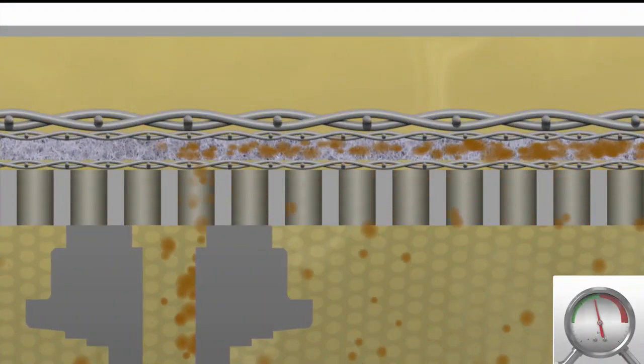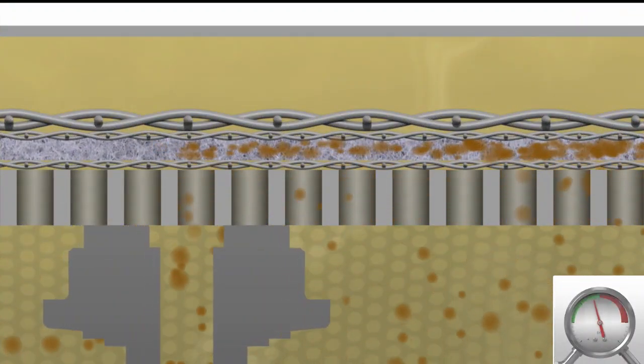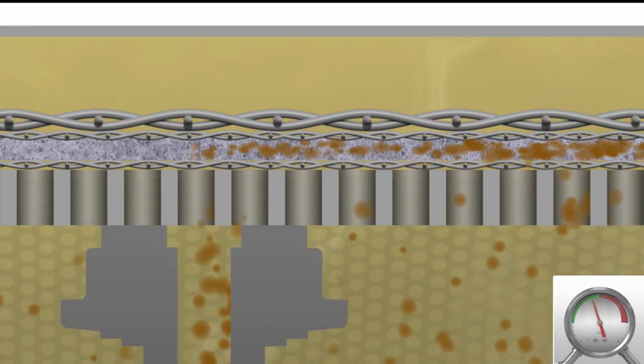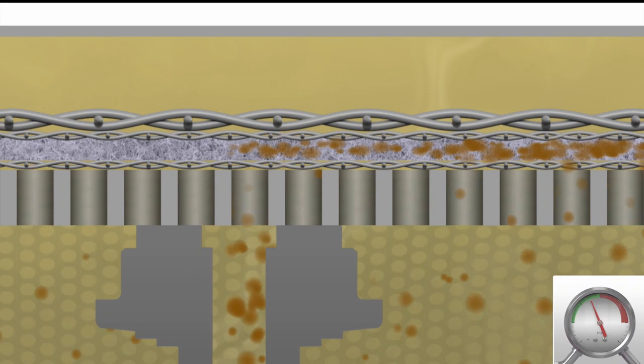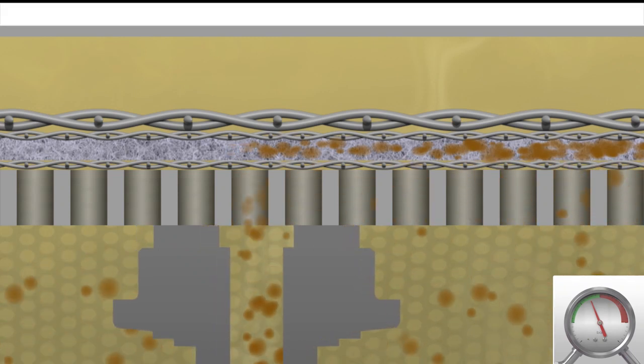The reject valve opens and the backwash pistons move linearly over the entire filter surface. Depending on the viscosity of the fluid, this process takes between 30 seconds and several minutes.